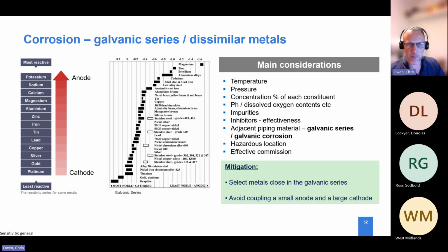The zinc sits more towards the anodic range of the series, so it's going to sacrifice itself to protect the steel, which is not necessarily a bad thing, because the zinc corrodes at a much slower rate. The zinc oxide produced is not as harmful to an installation as the iron oxide from rust. So the zinc sacrifices itself to protect the carbon steel.